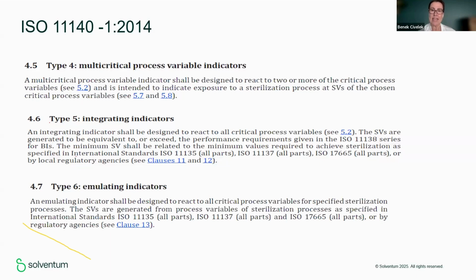So therefore, while selecting a type, we have to take care of the definition and which we will need. Because you may think that type 6 is also a multi-critical with three variables confirming, but still this is for specified cycles. So when a type 6 changes color, it means that at this pack, steam has reached that temperature for that time. But when we talk about type 5, we mean it to be used in every cycle, starting from 121 to 134, and it will sense the steam quality inside every pack, and it will either change color or, most favorably, there will also be an accept window where you can see the pass results.